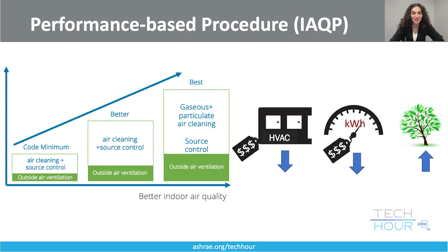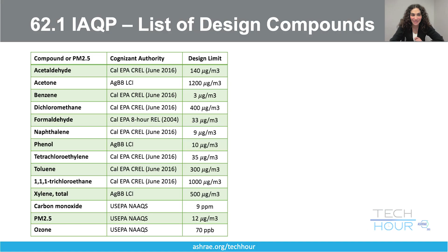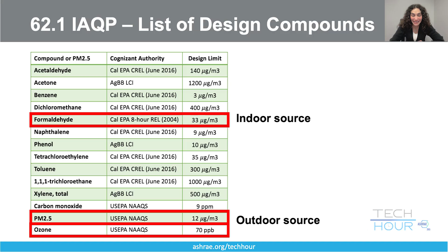And just so you know, in ASHRAE Standard 62.1, we have a list of design compounds. It's the first major list we have in an actual minimum standard adopted by building codes, a list of pollutants. There are volatile organic compounds, inorganics, and also PM 2.5. Now, what you need to know is that although there's a list, cognizant authority, and design limit, in practice, the pollutants that most often drive the calculations are only three: formaldehyde, which is a primary indoor source, and PM 2.5 and ozone, which are typically outdoor sources if you talk specifically about commercial buildings. So if you take these into consideration, the calculation becomes much more straightforward.